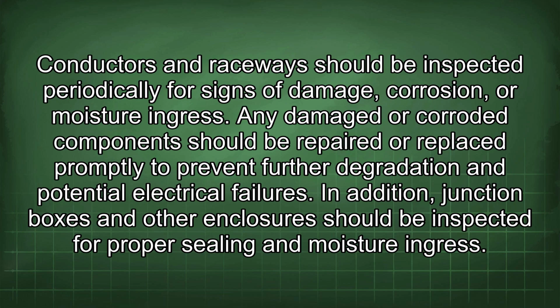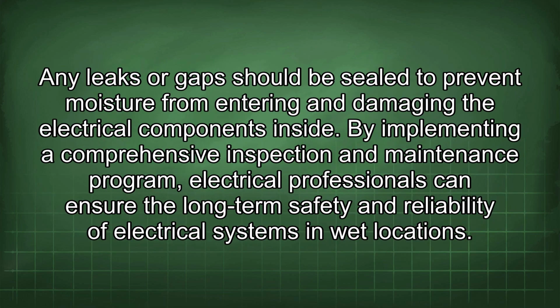Conductors and raceways should be inspected periodically for signs of damage, corrosion, or moisture ingress. Any damaged or corroded components should be repaired or replaced promptly to prevent further degradation and potential electrical failures. In addition, junction boxes and other enclosures should be inspected for proper sealing and moisture ingress. Any leaks or gaps should be sealed to prevent moisture from entering and damaging the electrical components inside.